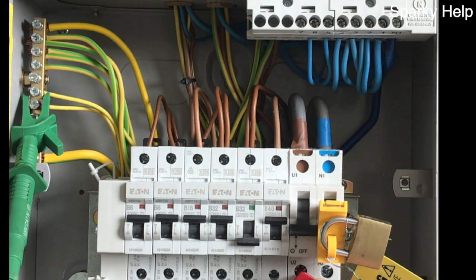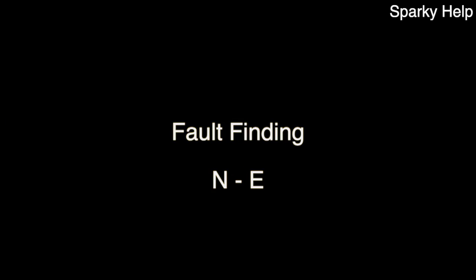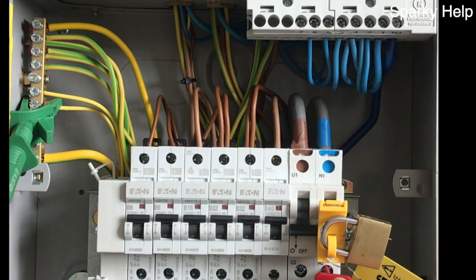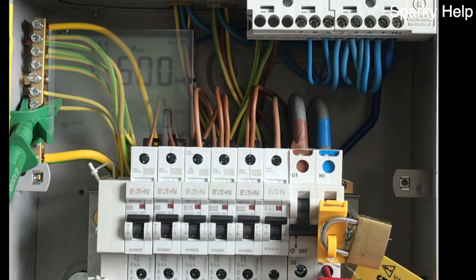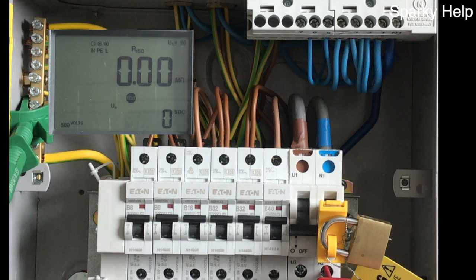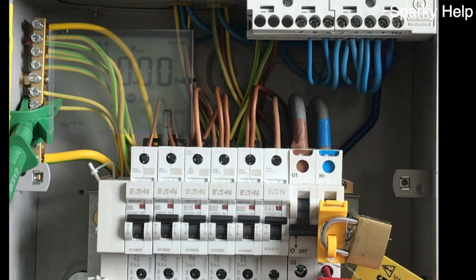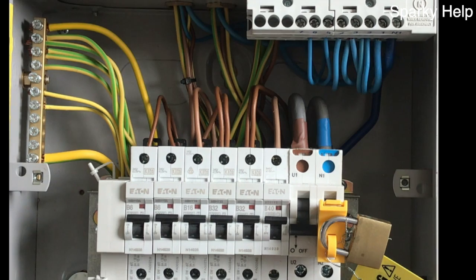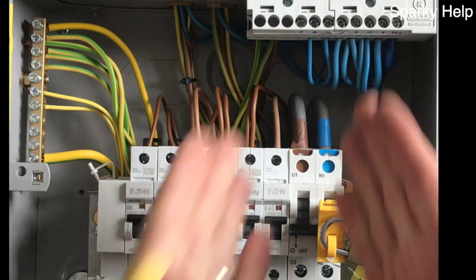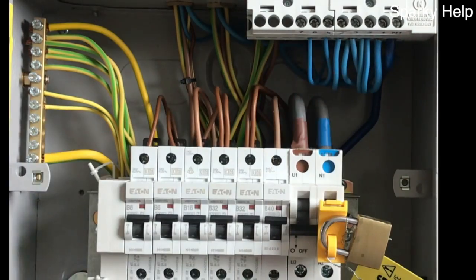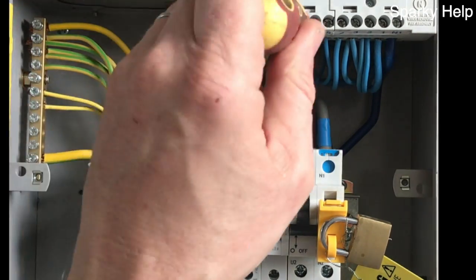First things first though, double check, make sure you've got nothing plugged in. So neutral to earth, and we've got 0, 0, 0, which means there's a dead short between neutral and earth. Unlike before, where we could turn the breakers off, we can't do that now. So what we need to do now is we need to take out these neutrals here. We can leave those intact, we don't need to touch those because it's neutral to earth, and so therefore we've got to go through these one at a time.